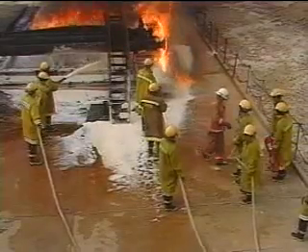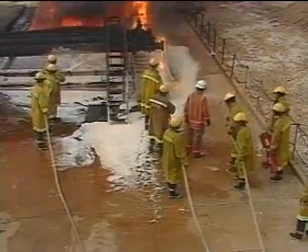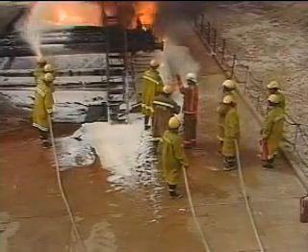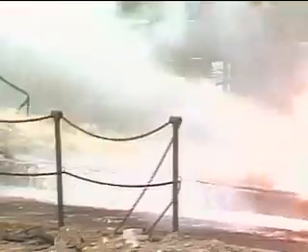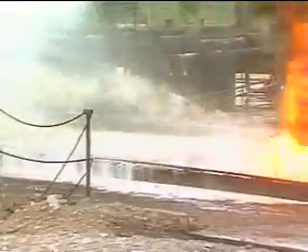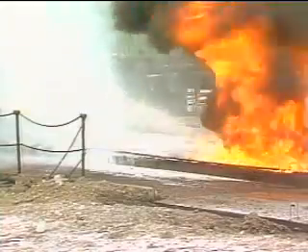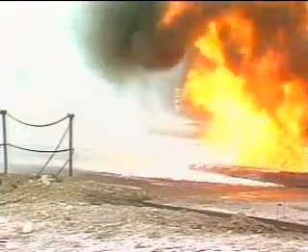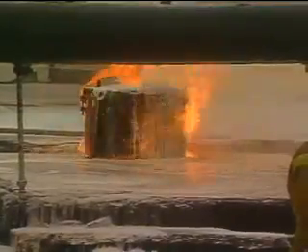During a fire, the foam should be gently applied on top of the fire. If possible, direct the foam at a wall or other braking device, allowing the foam to gently roll back over the fire. Avoid aiming the foam directly into the liquid. This will only splash the fire and make matters worse.